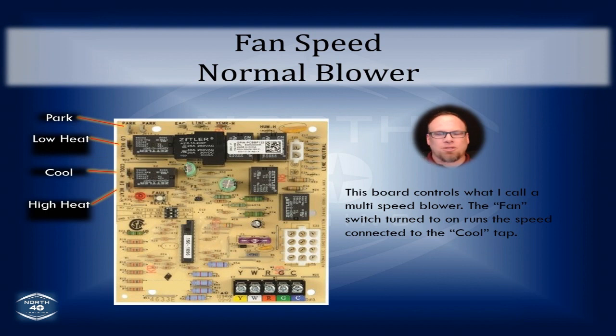Your fan speeds, traditionally, as we were just looking at on the manufacturer's guidelines that I just had pulled up a minute ago, you had four fan speeds. You had the high, you had the medium, then you had medium low, and then you had low. Okay, so if you look at this board, you've got a spot for your high heat, your cool, your low heat, and then there's two up at the top left-hand corner. They're called park. Park is not energized. It's a place for you to put any spare fan speeds that you don't want energized, and it's in lieu of the way we used to do things. The way we used to do things was to just tape it up and leave it hang or strap it to another bundle of wires. Okay, now you just run that to the board and that's an unenergized terminal.